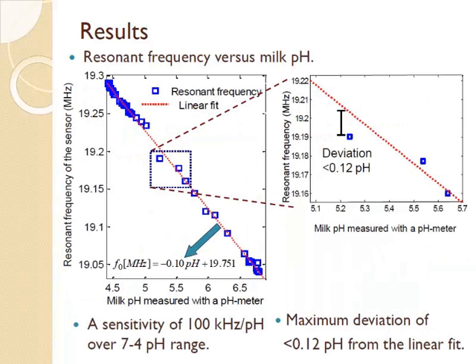Then we plotted the resonant frequency versus the pH measured by the commercial pH probe, and we found that the relationship between them looks very linear. From the linear fit, you can see we have almost 100 kilohertz per pH sensitivity, and the maximum deviation from the linear fit was around 0.12 pH.